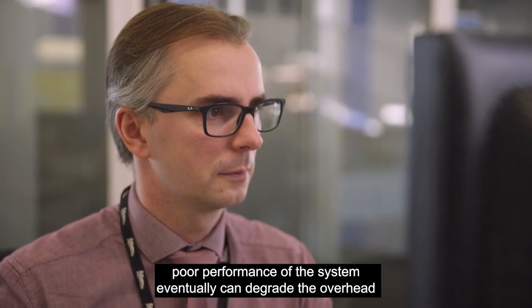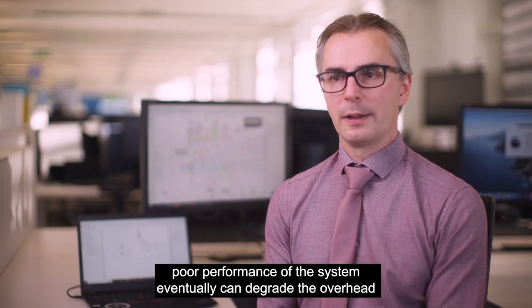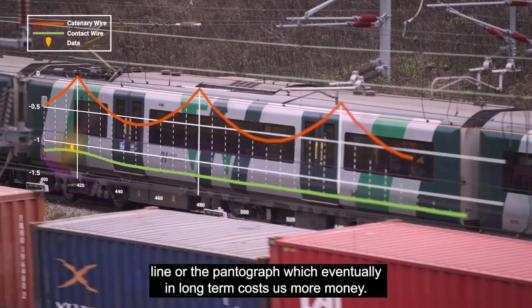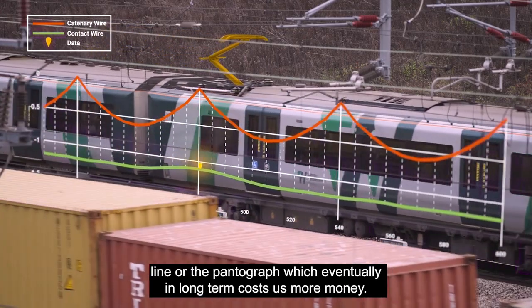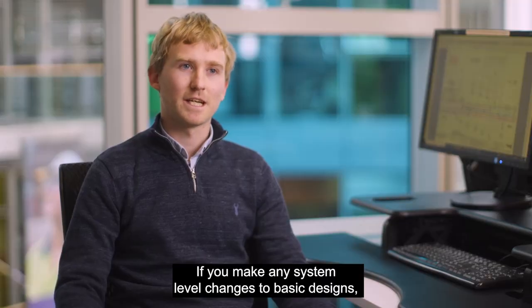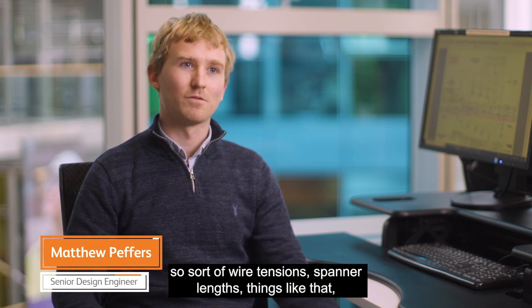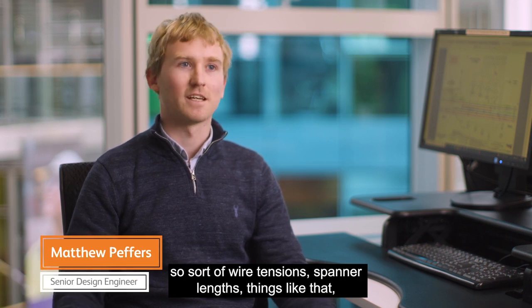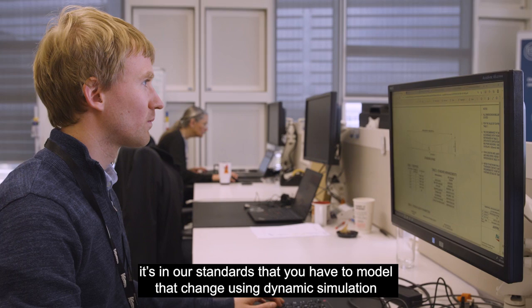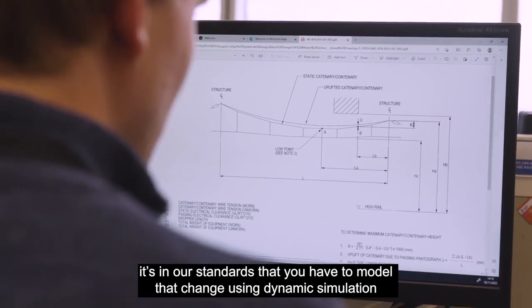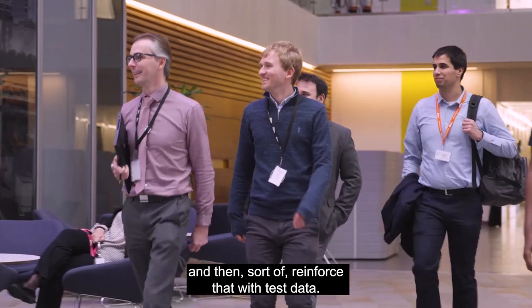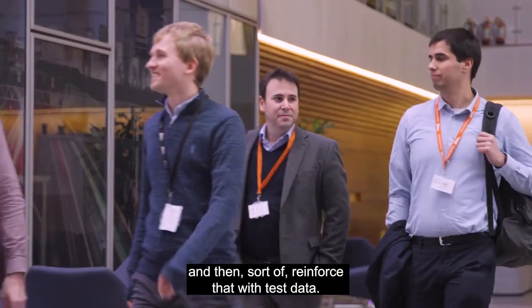Poor performance of the system can eventually degrade the overhead line or the pantograph, which in the long term costs us more money. If you make any system level changes to the basic design, so wire tensions, span lengths, things like that, it's in our standards that you have to model that change using dynamic simulation and then reinforce that with test data.